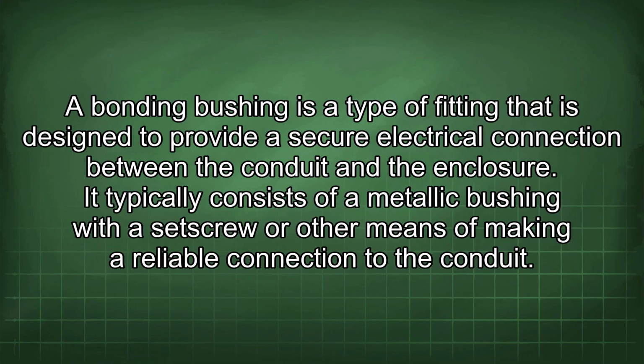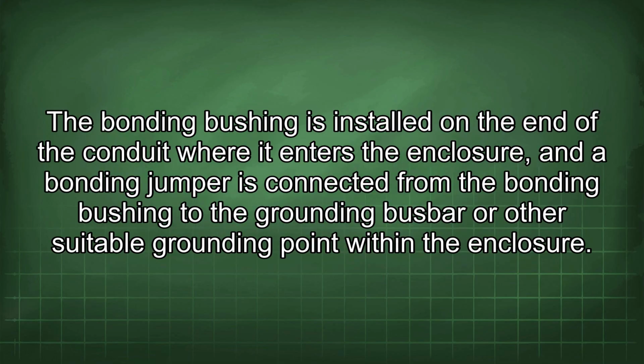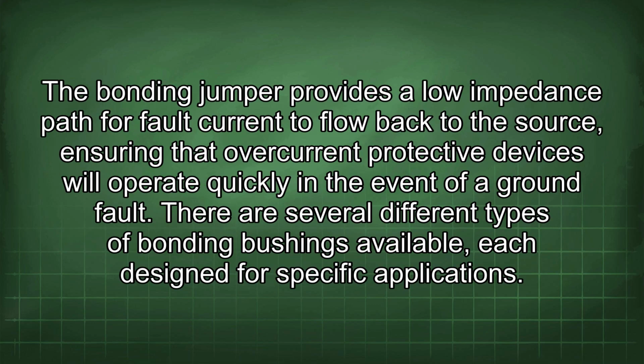It typically consists of a metallic bushing with a set screw or other means of making a reliable connection to the conduit. The bonding bushing is installed on the end of the conduit where it enters the enclosure, and a bonding jumper is connected from the bonding bushing to the grounding busbar or other suitable grounding point within the enclosure. The bonding jumper provides a low impedance path for fault current to flow back to the source, ensuring that overcurrent protective devices will operate quickly in the event of a ground fault.